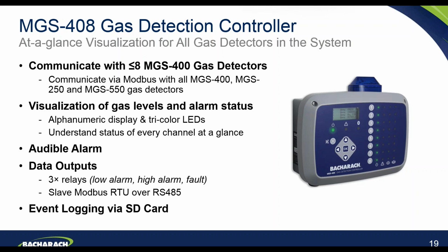It provides alphanumeric display and tricolor LEDs for each of the gas detectors connected. So it's very simple at a glance to understand the status of each channel, whether it's an alarm condition, a fault condition, for example, or just a standard power. The control panel features an audible alarm. You can see there's also a visual alarm option, which, as you can see on the image on the right-hand side, is mounted to the top of the case. The control panel features 3 relays, again to mirror the relay capability of the detectors themselves. So you have a low alarm, a high alarm, and a fault relay.